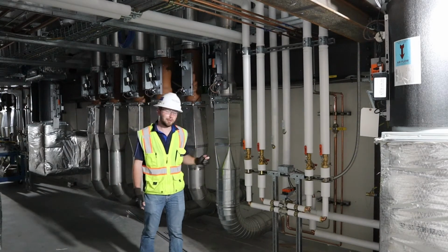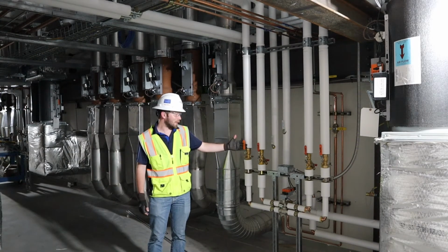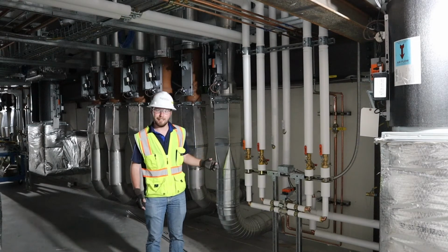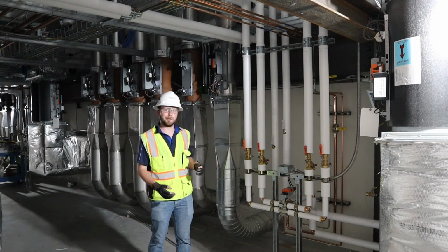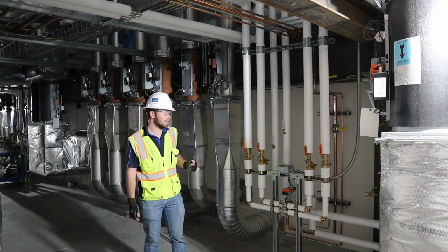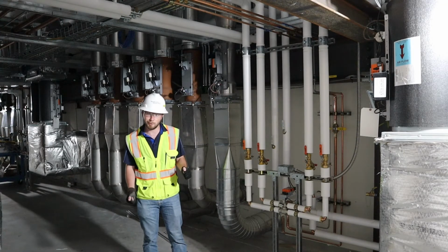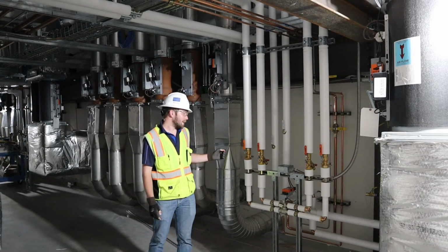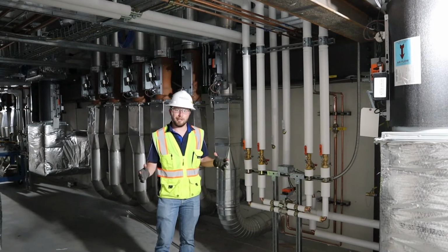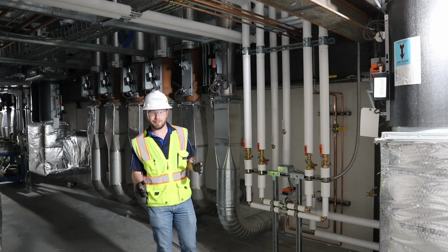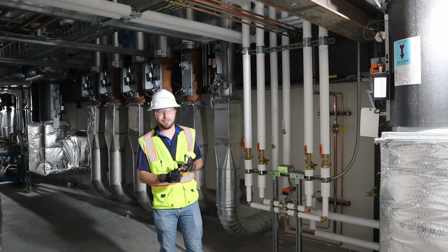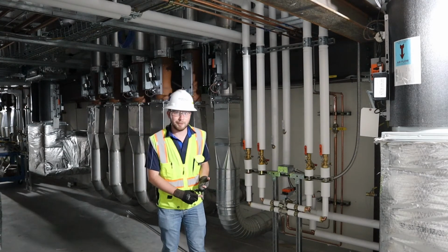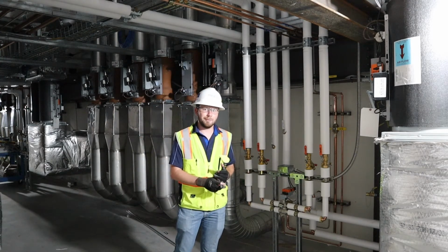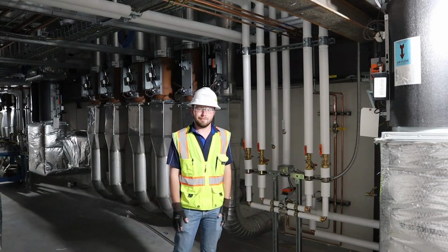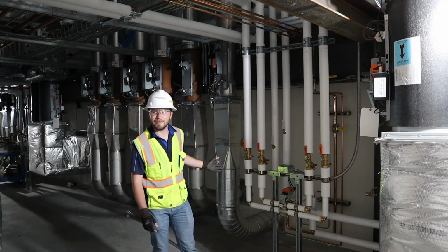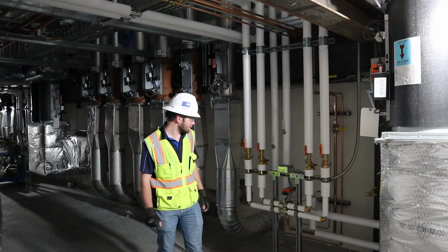And like I was saying earlier, we had to place each of the valves in the BIM model so we could show the owner, fly the owner through, show them where everything was going to be so they could see that was all accessible. Not only that, but we have to label each one of these, have a master spreadsheet with 2,500 valves on it that has the location, what it serves, its normal operating position, and the valve tag number. And now we have to go through and put the tag on each one of these valves.